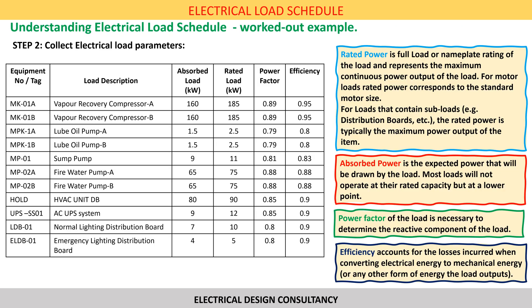Once we have the preliminary list of loads, we need to collect the electrical parameters like the rated power, absorbed power, power factor and efficiency. Rated power is the full load or nameplate rating of the load and represents the maximum continuous power output of the load. For motor loads, rated power corresponds to the standard motor size. For loads that contain sub-loads like distribution boards, the rated power is typically the maximum power output with all sub-loads in service.